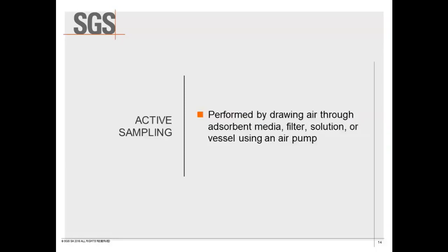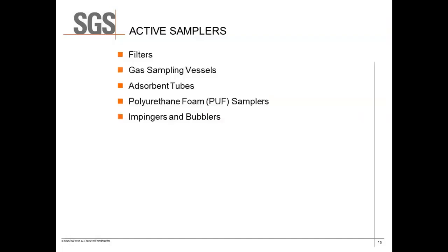Active sampling is performed by drawing air through an adsorbent media, filter, solution, or vessel, typically using an air pump or, in the case of a canister, under vacuum. Active samplers primarily consist of filters, gas sampling vessels, adsorbent tubes — broken into thermal desorption tubes and solvent desorption tubes — polyurethane foam PUF samplers, and impingers and bubblers.